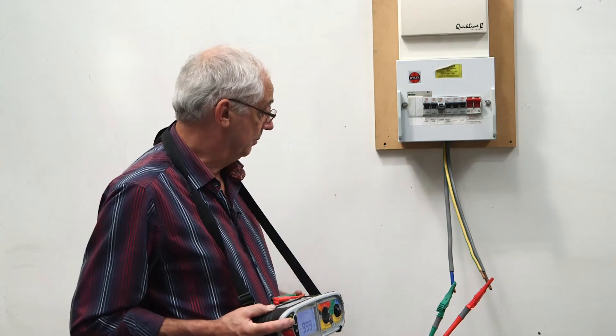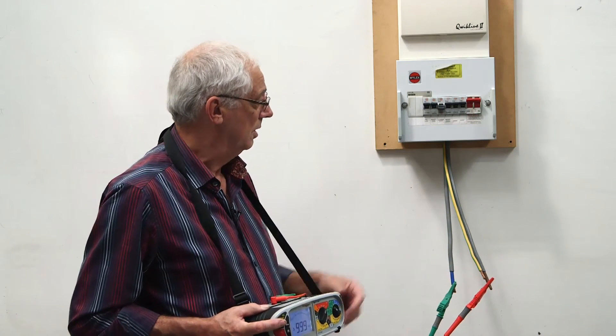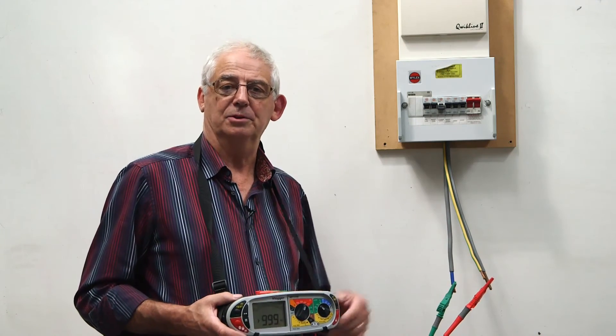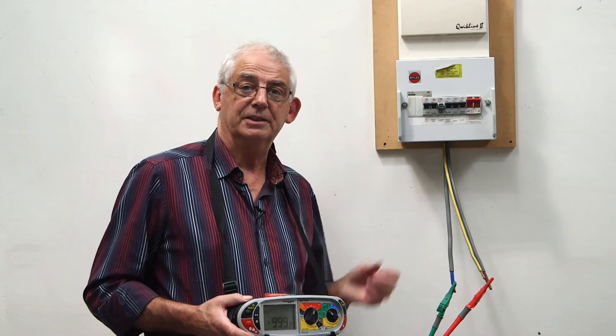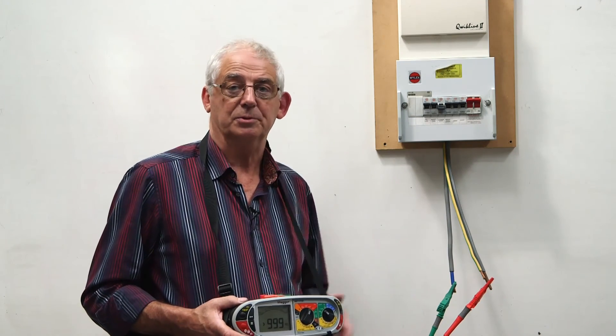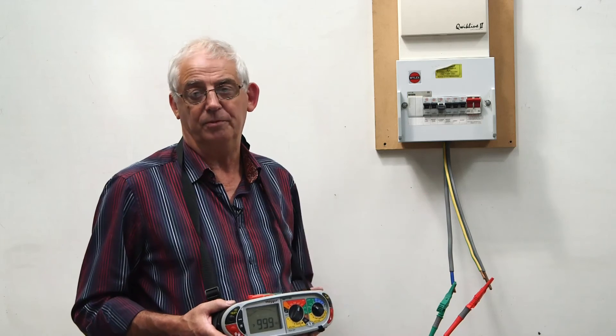At that point, because it's between line and neutral, I may want to look up in the airing cupboard just to make sure that the immersion heater is not switched on or possibly there's a neon indicator lamp on the switch. So that would be the first place I would look.